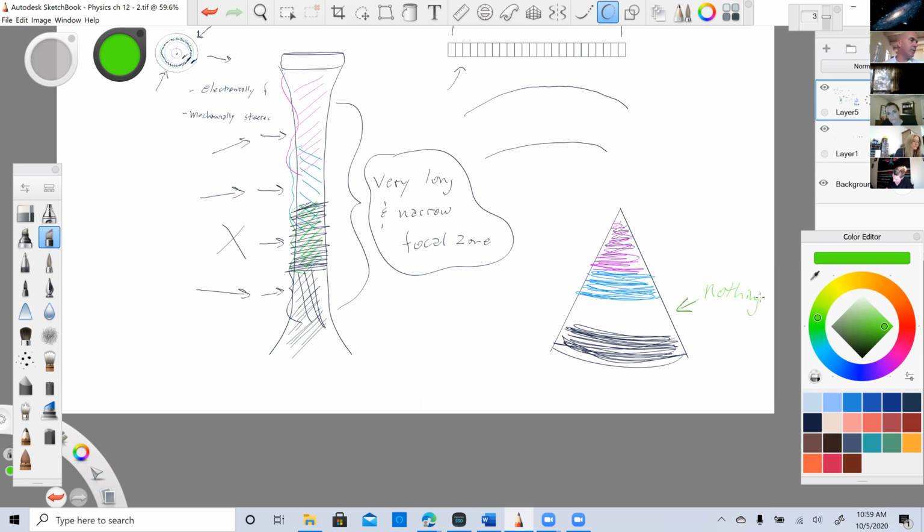So a damaged PZT crystal, first of all, image shape, fan, or sector. Damaged crystal, this will appear as a horizontal side-to-side band of dropout at a particular depth. Recall that each ring of an annular array is responsible for collecting image data from its focal zone.